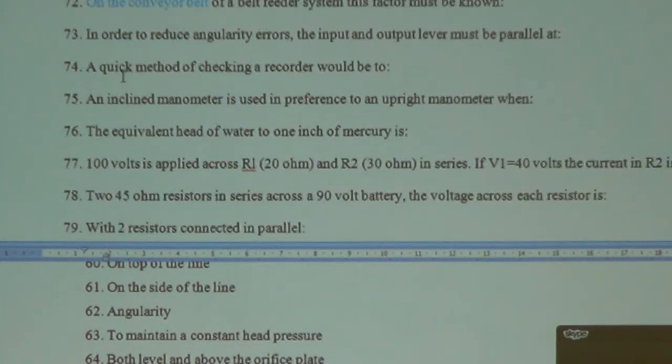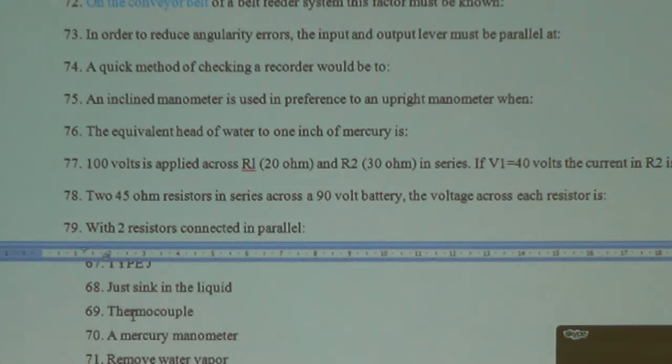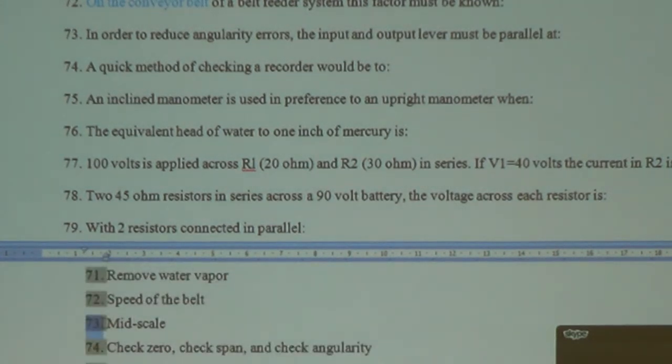In order to reduce the angularity errors, the input and output levers must be parallel at mid-scale. Remember, we do squaring - squaring is done for mid-scale adjustments.